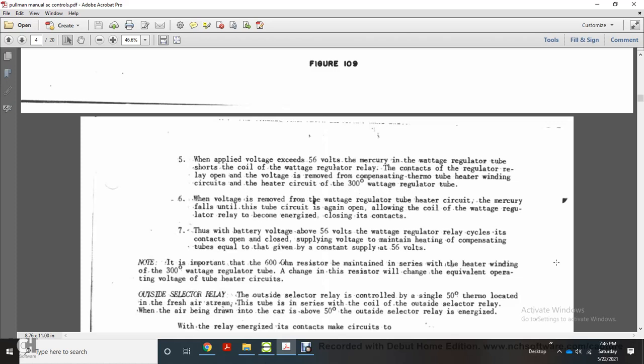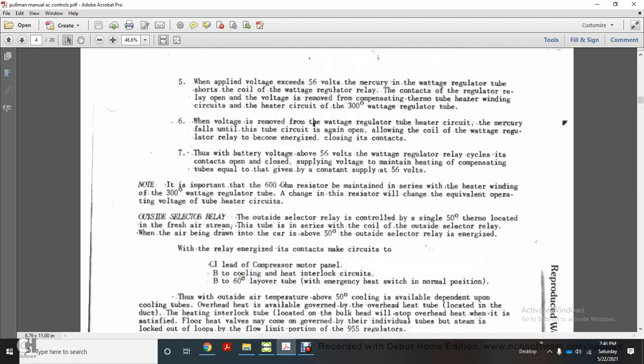Thus, with battery voltage above 56 volts, the watt regulator relay cycles its contacts open and closed, supplying voltage to the main heating compensating tube equivalent to a constant supply of 56 volts. Note: it is important for the 600-ohm resistor to maintain the heater winding of the 300-degree watt regulator tube. Changing the resistor will change the equivalent operating voltage of the tube heater circuit. The outside selector relay is controlled by a single 50-degree thermostat located within the fresh air system, in series with the coil of the outside selector relay, with air being drawn into the car at about 50 degrees.